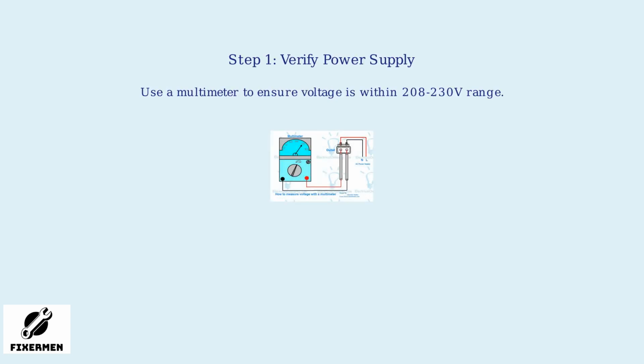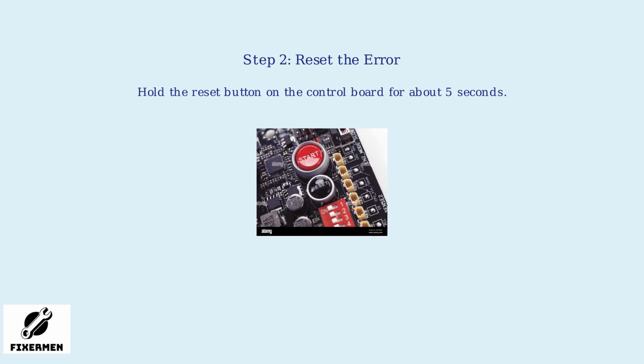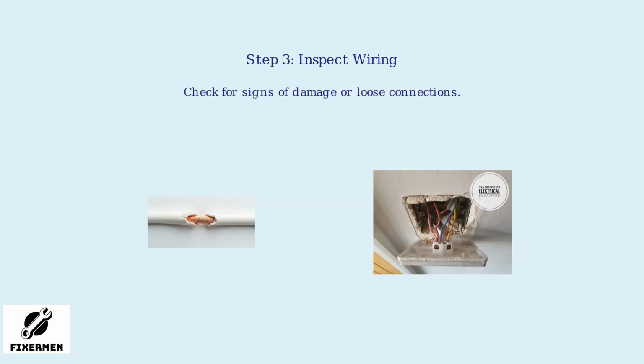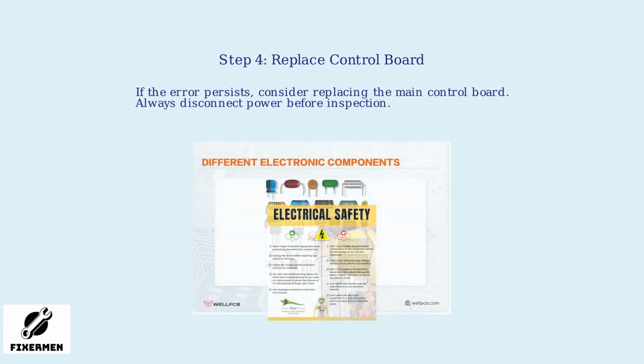First, verify the power supply at the unit using a multimeter to ensure it's within the specified range of 208 to 230 volts. Second, reset the error by holding the reset button on the control board for about 5 seconds. Third, inspect the wiring for any signs of damage or loose connections. Fourth, if the error persists, consider replacing the main control board. Always disconnect power before any inspection to avoid electrical shock.